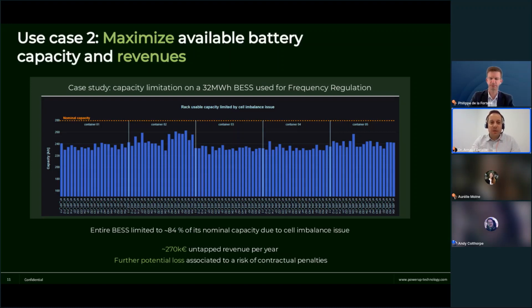In this example, we analyzed data from a 32 megawatt hour battery asset used for frequency regulation. What we see on this graph is the available capacity of all the racks in blue compared to the nominal capacity expected, shown in orange.